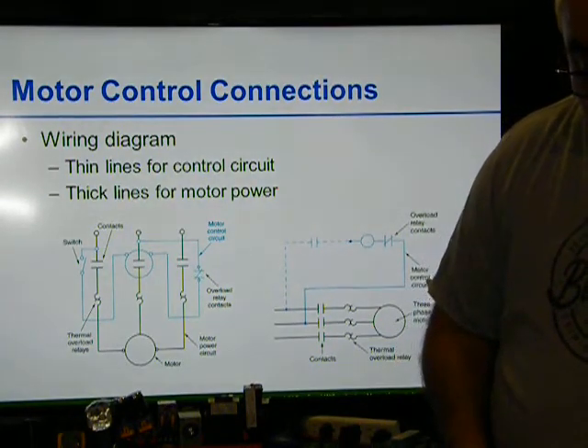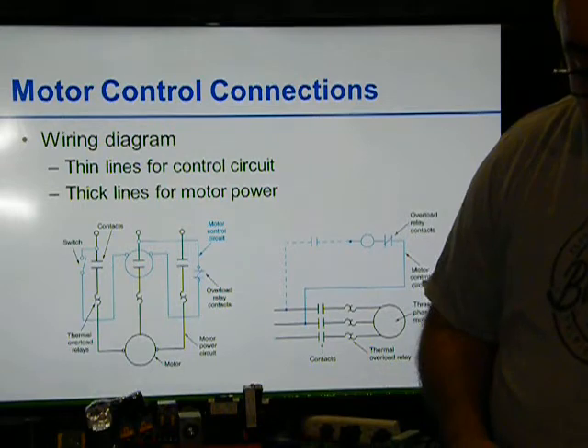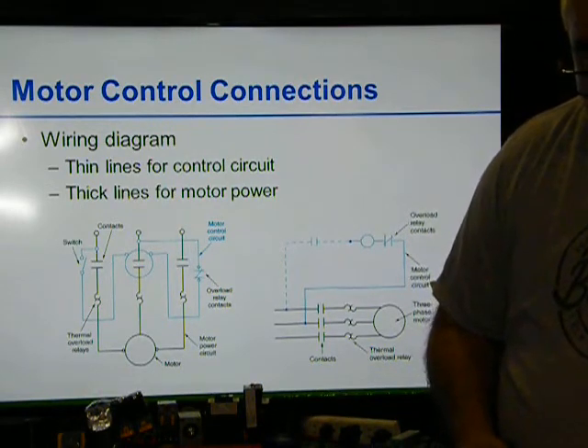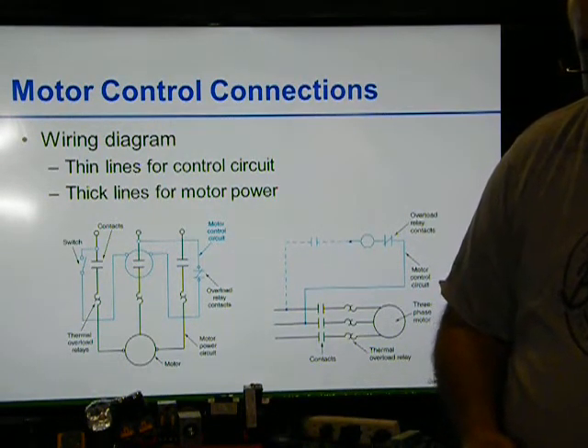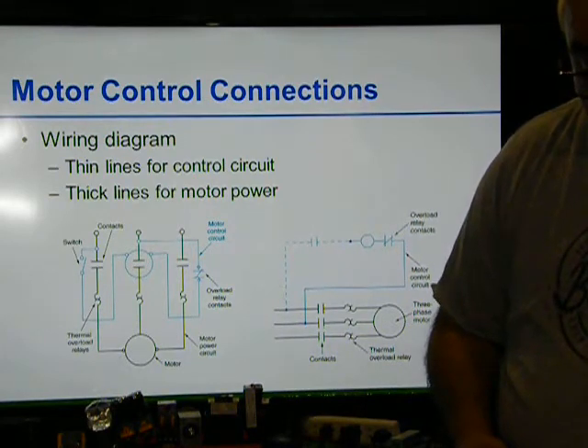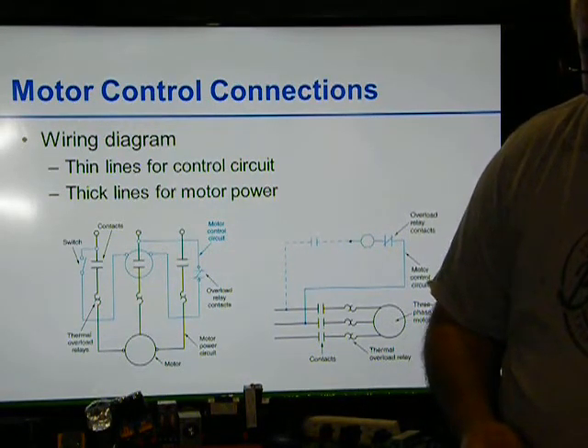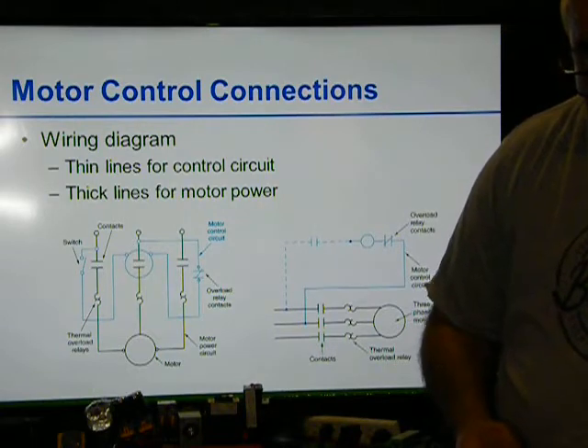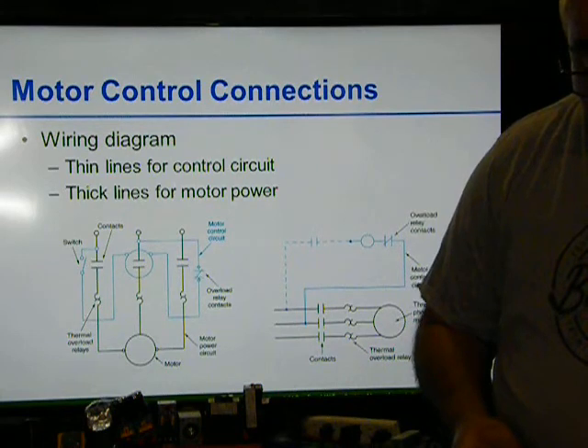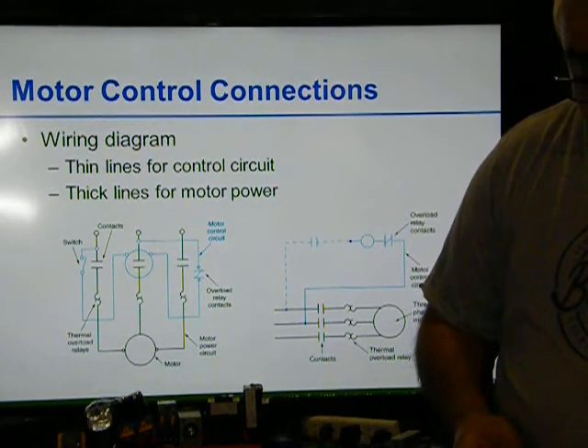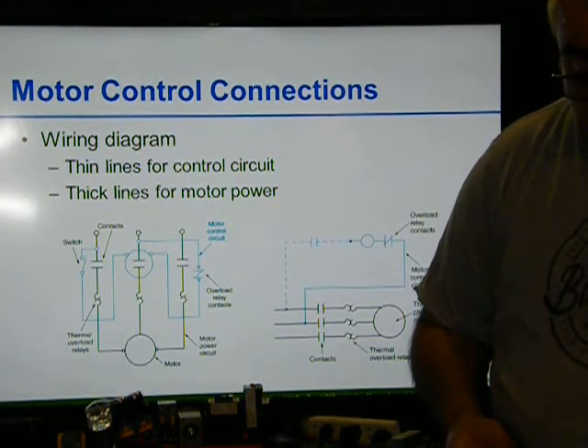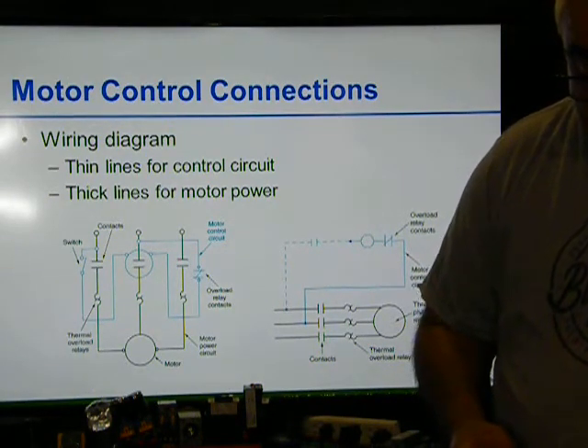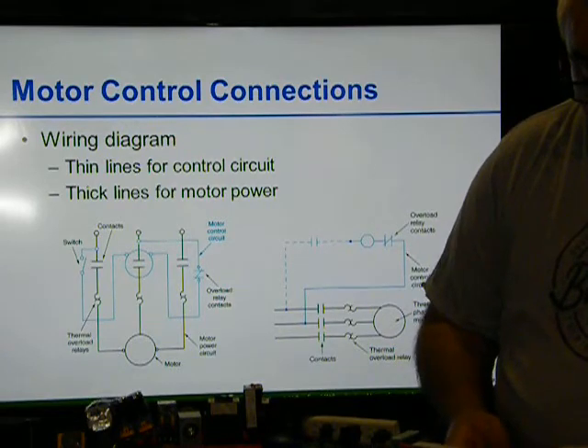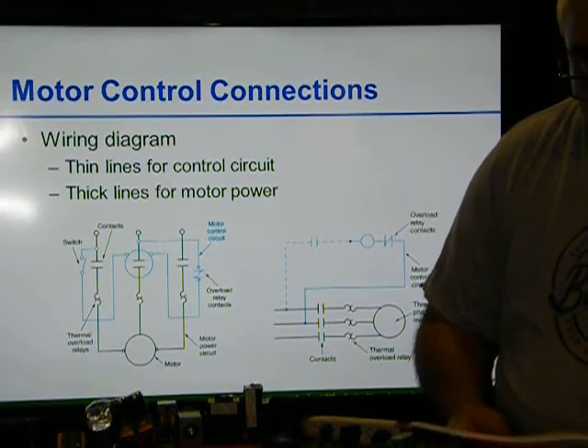It says contacts shown refer to normally open, which will close when energized. These contacts shown closed in the diagram will open when energized and are called normally closed. Overload relays can open or close depending on whether their associated relays are open or closed. The control circuit in its most basic form, without a power circuit, is illustrated by figure 14.6. Three components of the starter.